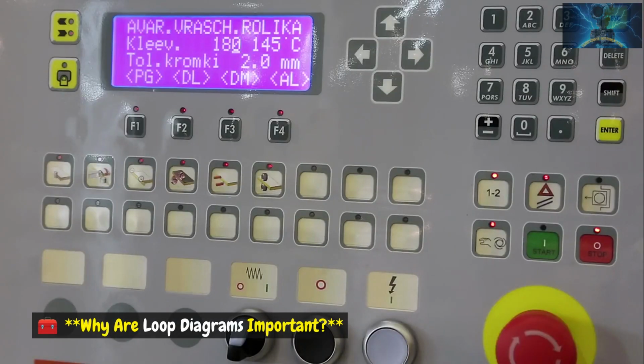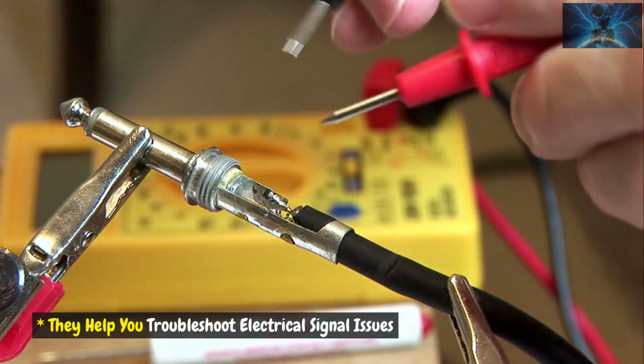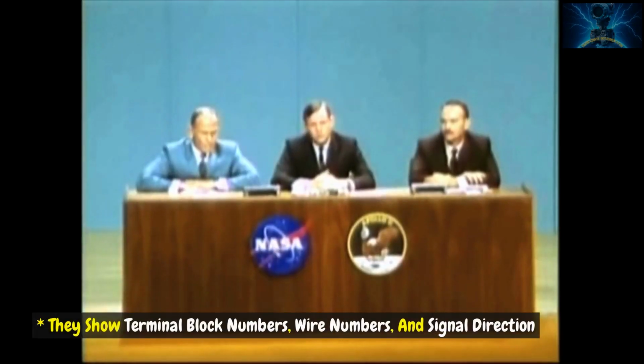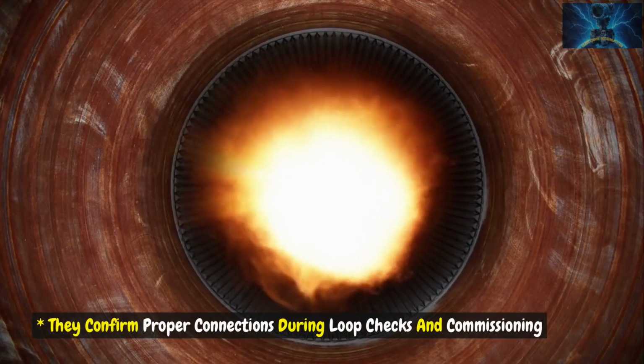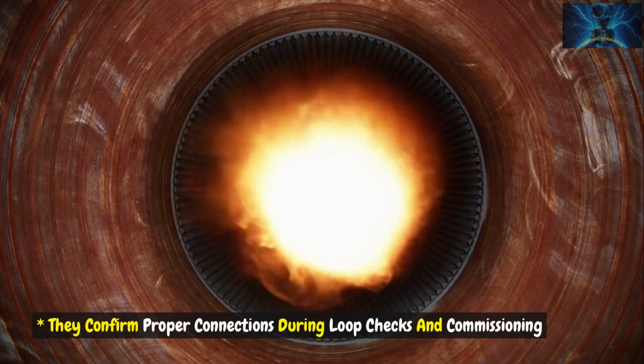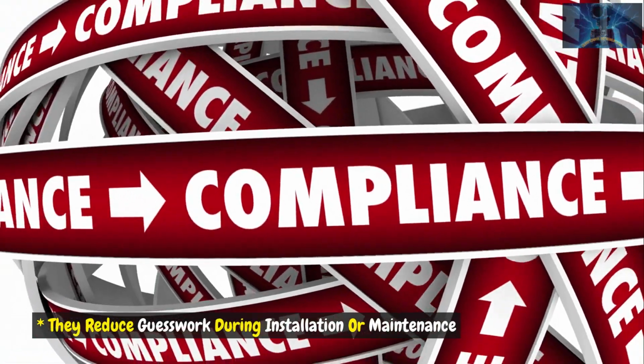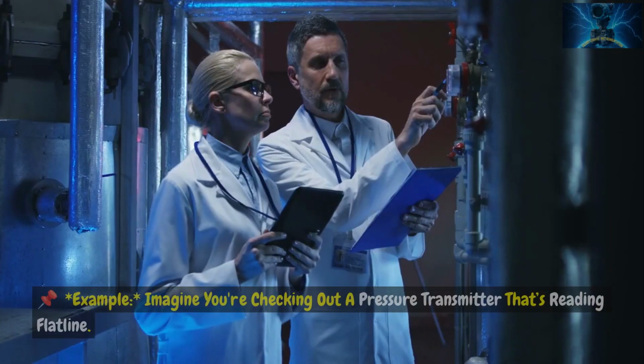Why are loop diagrams important? They help you troubleshoot electrical signal issues. They show terminal block numbers, wire numbers, and signal direction. They confirm proper connections during loop checks and commissioning. They reduce guesswork during installation or maintenance.